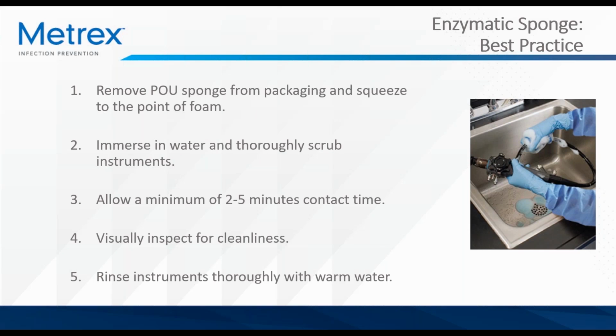Next, we'll talk about enzymatic sponge best practice. First step when using an enzymatic sponge is to remove the sponge from its packaging and squeeze to the point of foam. Next, you'll want to immerse the sponge in water and begin scrubbing instruments. It's important to review the manufacturer's instructions for use, as some have recommended contact times, usually a minimum of 2 to 5 minutes. Visually inspect the instrument for cleanliness, paying particular attention to indents or crevices where debris may be hiding. Lastly, rinse the instruments thoroughly with warm water.